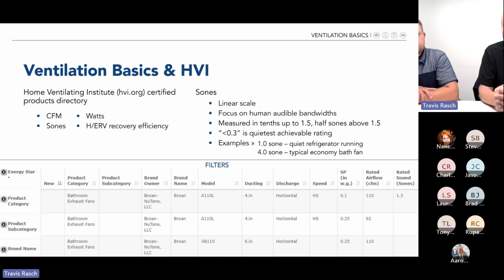You really want to look for products that are HVI certified. If they're not, you really just can't trust it. And more, the building codes are requiring HVI certification. Depending which version of the I codes your state or city is on, it's required that they be certified either for spot ventilation or, in the latest code, even for whole house ventilation. So very important. I touch on sones a little bit.